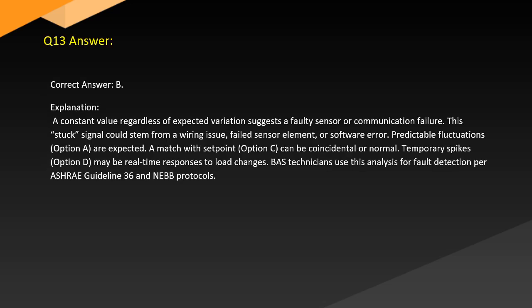Answer. Correct answer: B. Explanation. A constant value regardless of expected variation suggests a faulty sensor or communication failure. This stuck signal could stem from a wiring issue, failed sensor element, or software error. Predictable fluctuations, option A, are expected. A match with the set point, option C, can be coincidental or normal. Temporary spikes, option D, may be real-time responses to load changes.